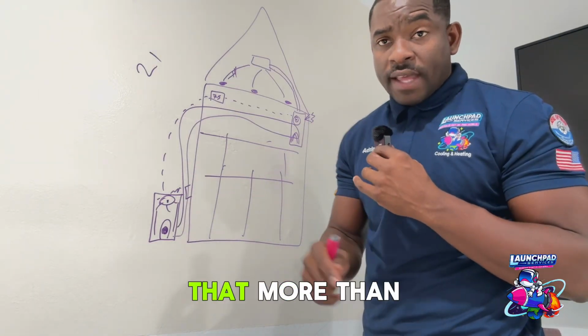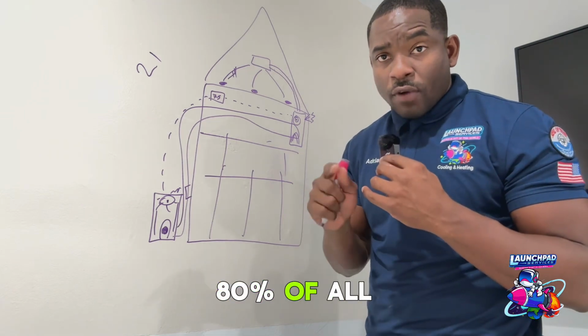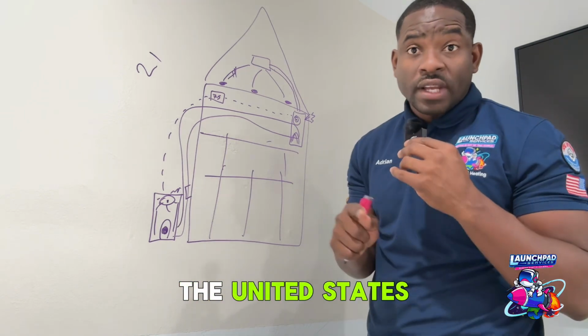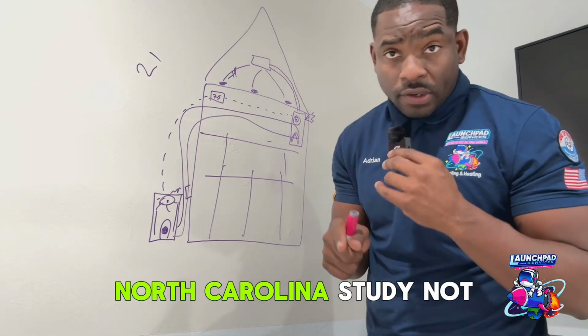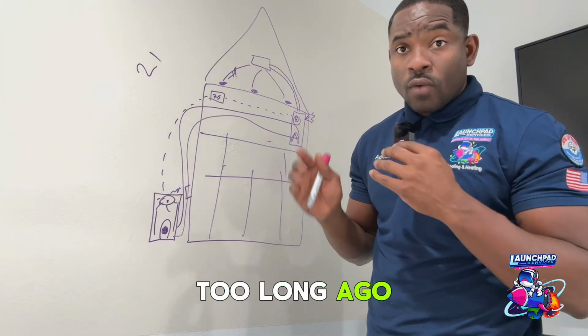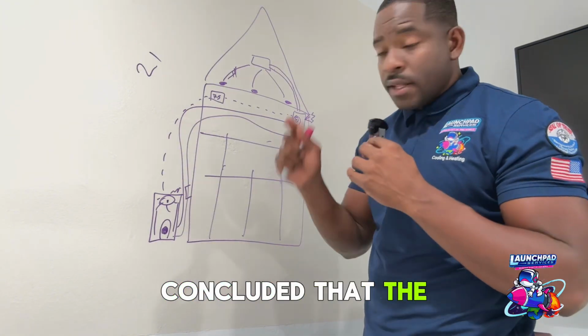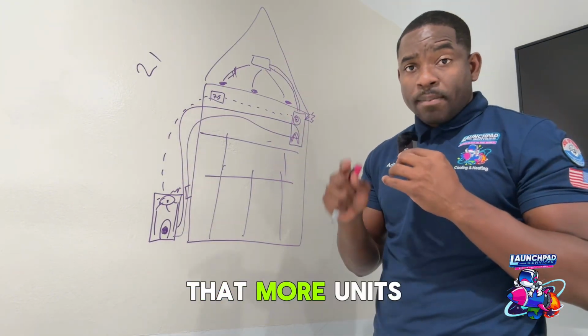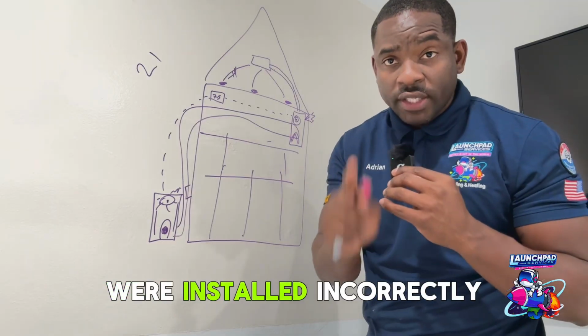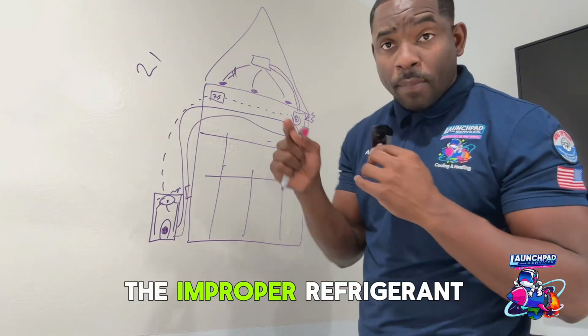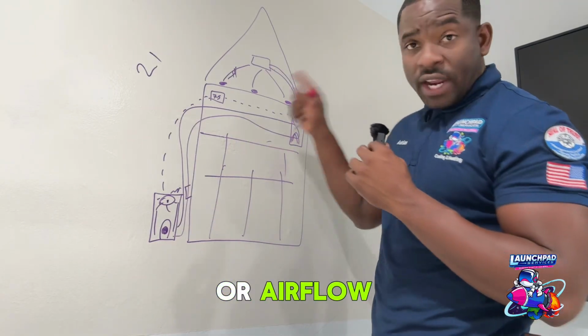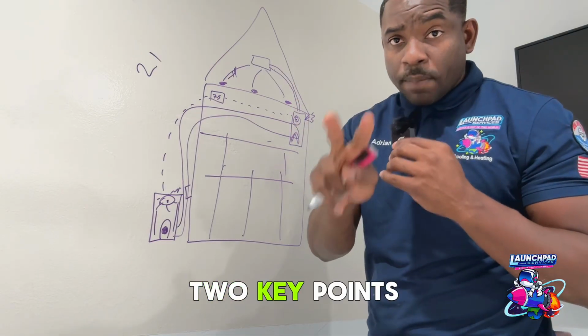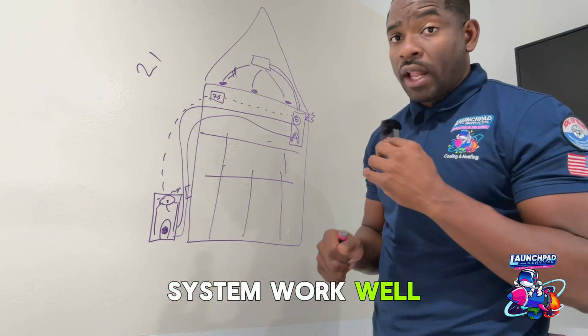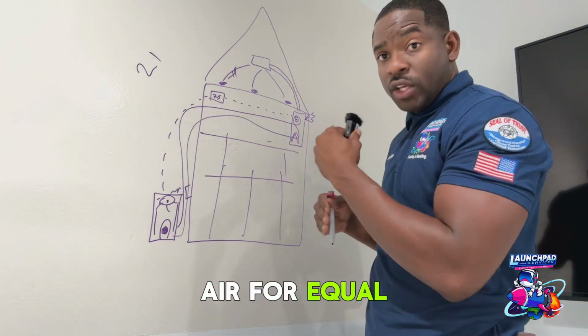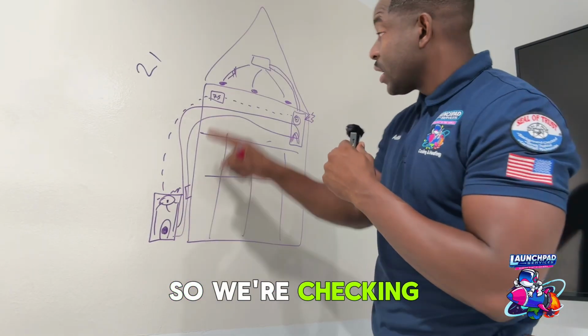Did you know that more than 80% of all units that were installed in the United States, according to a North Carolina study not too long ago, concluded that the number one reason that more units were installed incorrectly was because of improper refrigerant or airflow? Those are the two key points that make your system work well. We need equal air for equal refrigerant flow. So we're checking all of that.